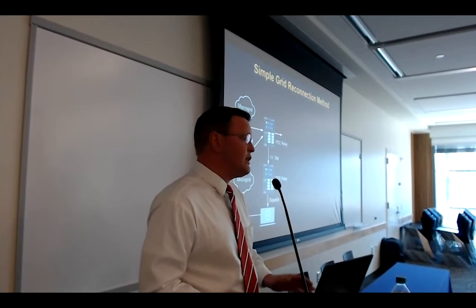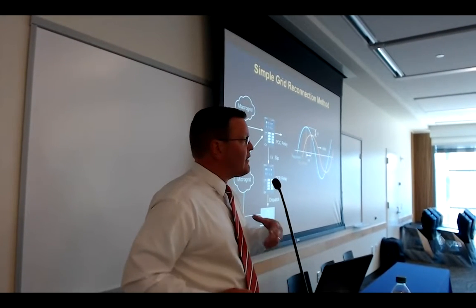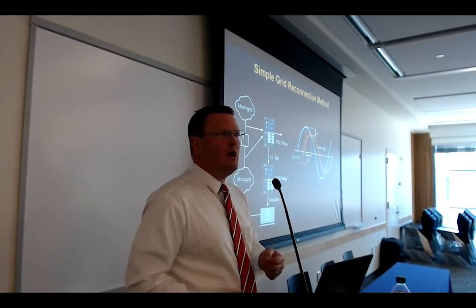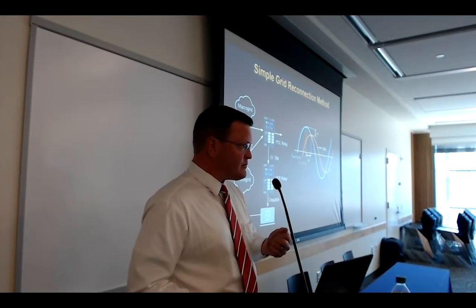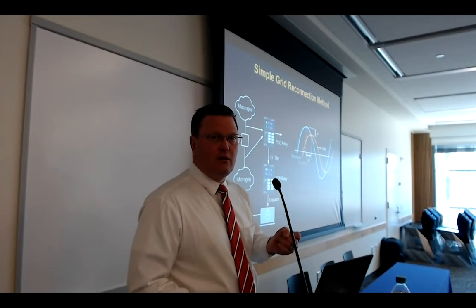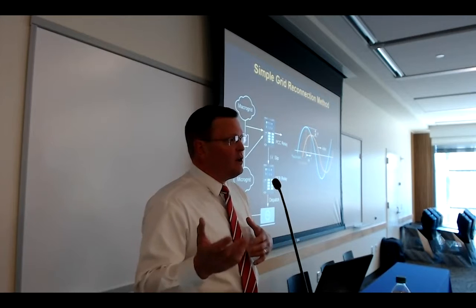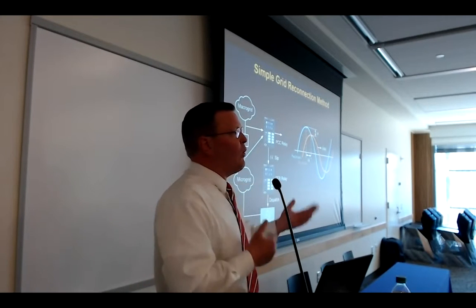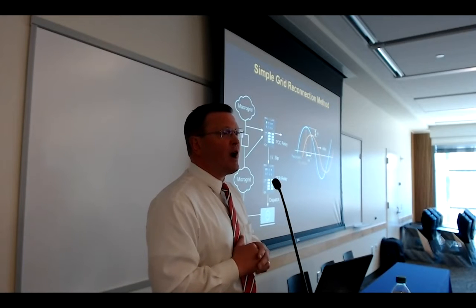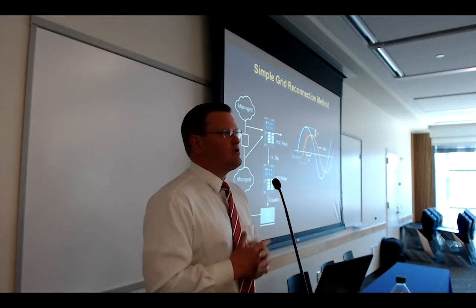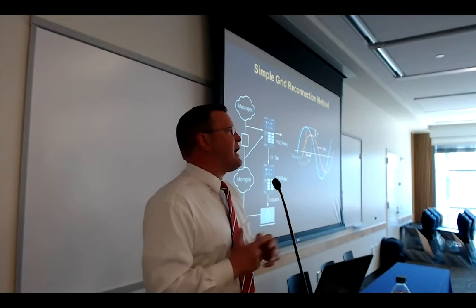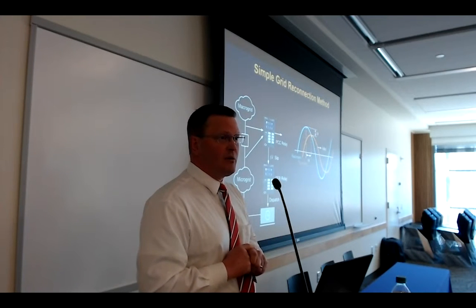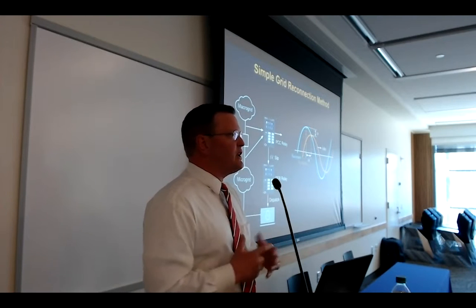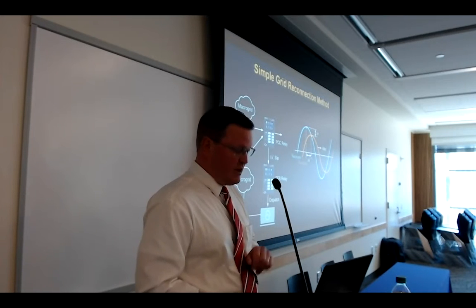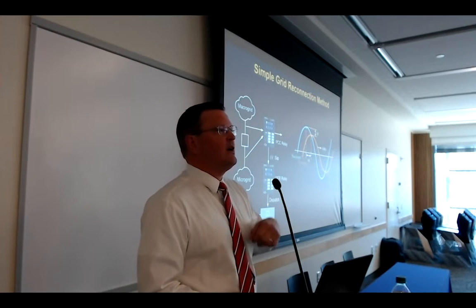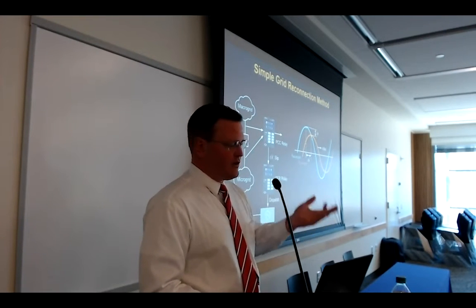These relays are lovely at doing synchronization. If you have to synchronize one or multiple breakers, you simply put a protective relay at every single point of interconnect, or point of common coupling. Basically one relay per DER, one relay per galvanic contractual isolation point. That relay measures the slip and the voltage angle, and it can dispatch those DERs for you to bring synchronization back in line. This is an everyday job for a relay today. Meanwhile, it also does protection, metering, IEEE compliance, et cetera, et cetera.